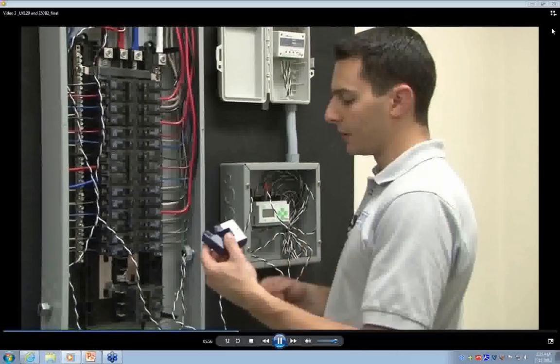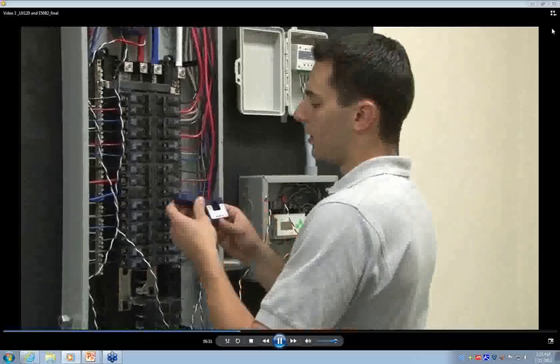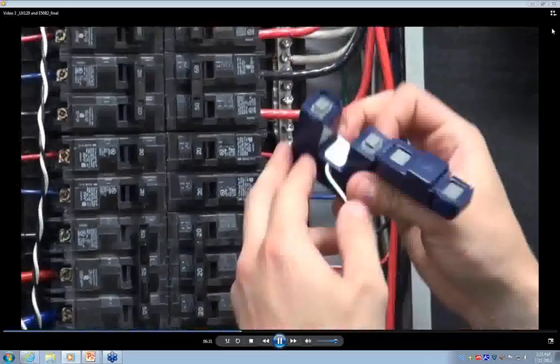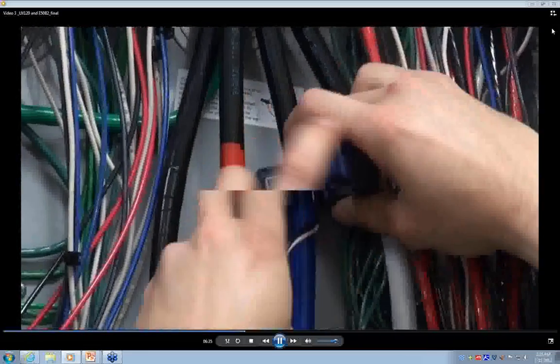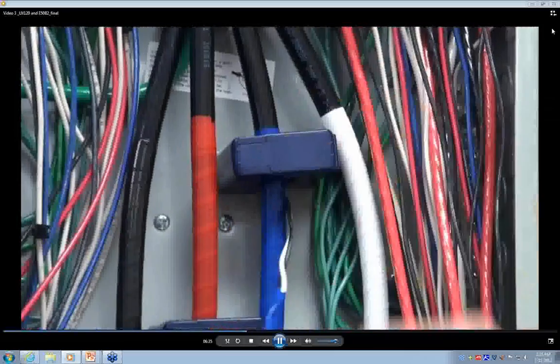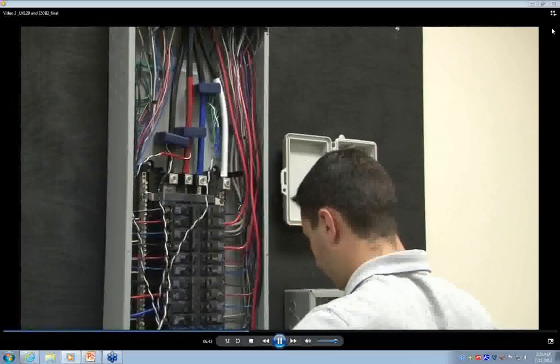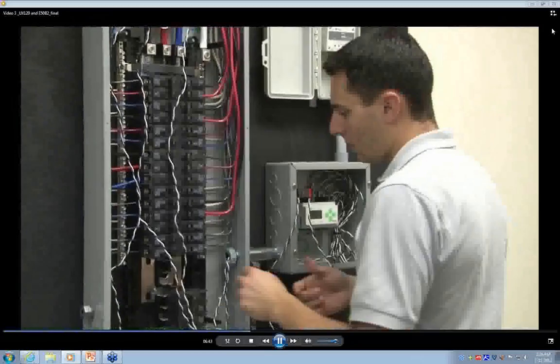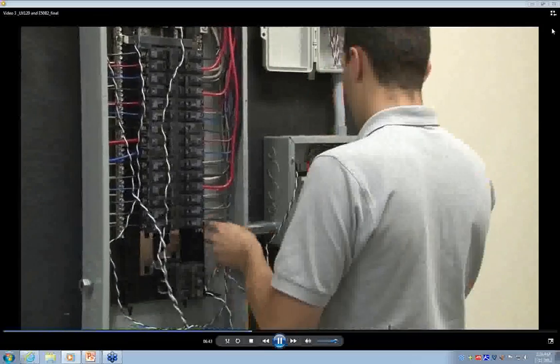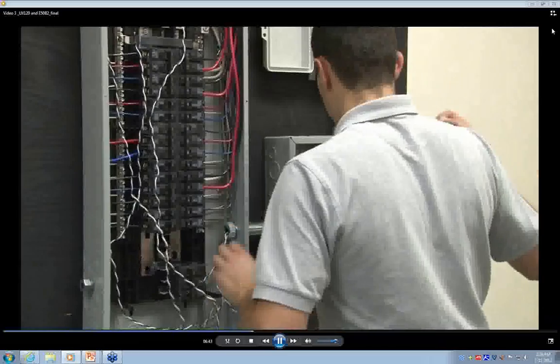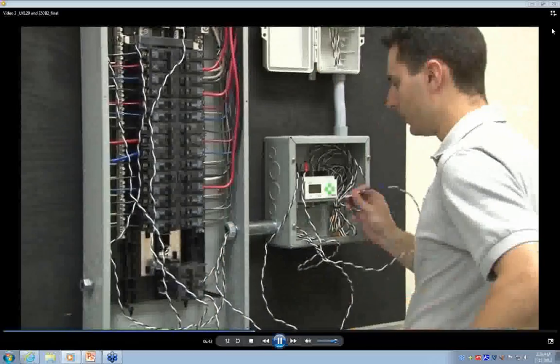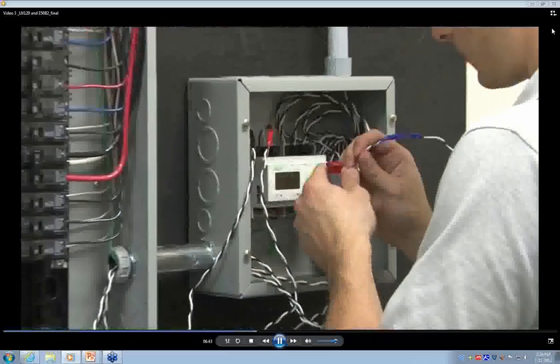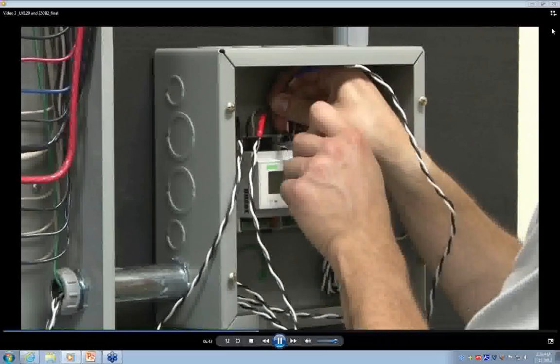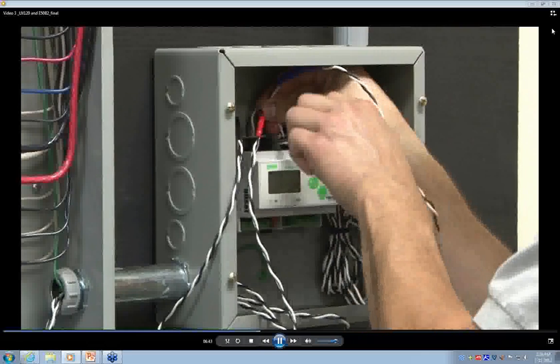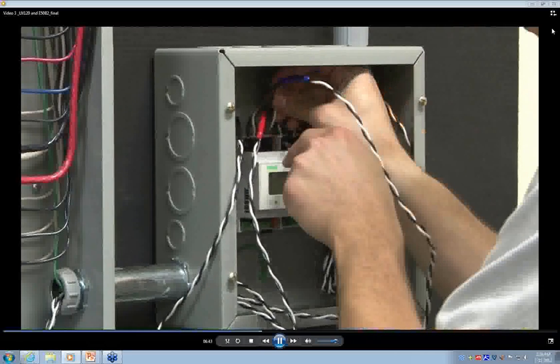Our final CT is the blue phase C CT. Once again, we line up the arrow with the source, connect the CT around the conductor, and clip it closed. We'll run our final CT conductor through the conduit to the phase C terminal of the E50B2. The black conductor once again will be connected to the negative terminal, and the white conductor will be connected to the positive terminal.